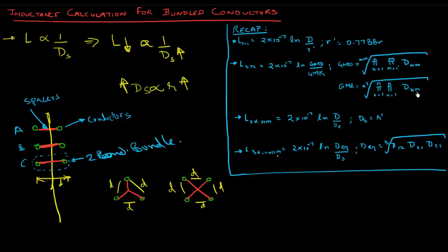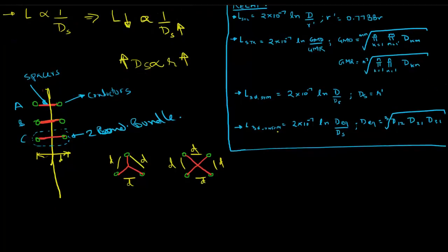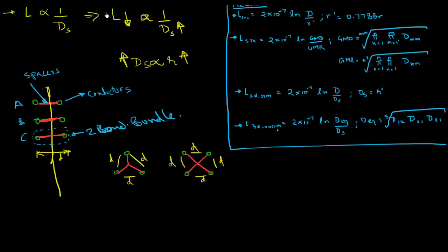And we'll see how they decrease the inductance because they will increase this value ds. They become similar to what we had with GMR formulation here, right? We will use this formulation to calculate ds. So this kind of configuration of bundle conductors is used specifically in extra high voltage lines.